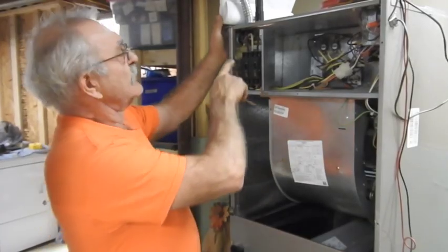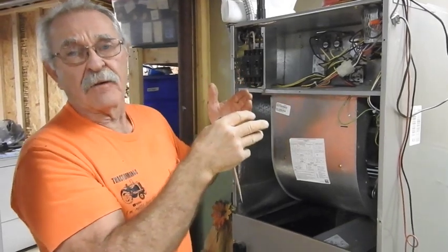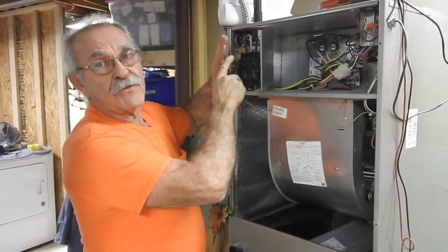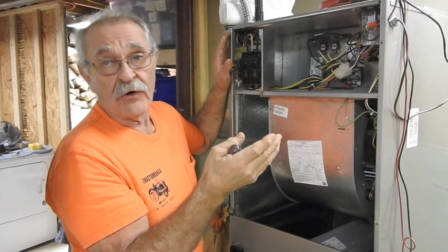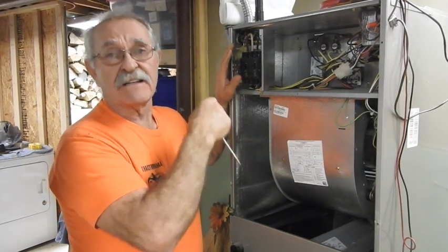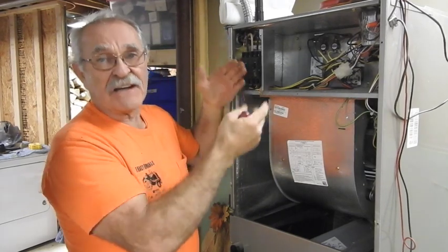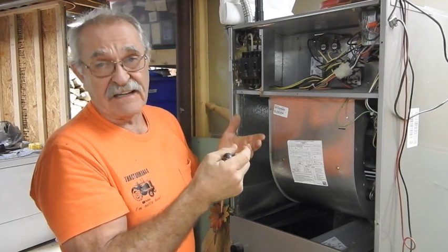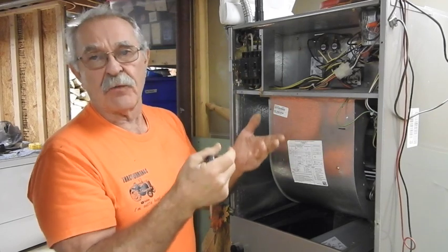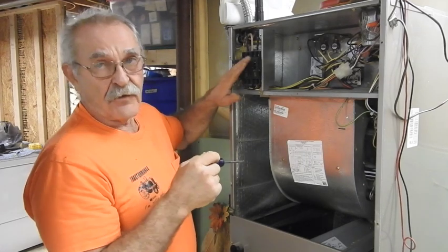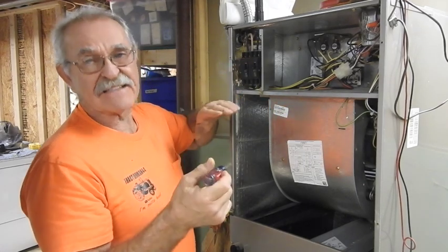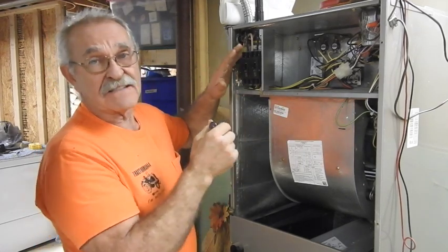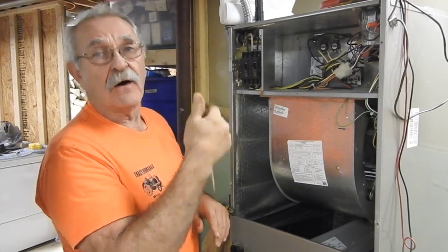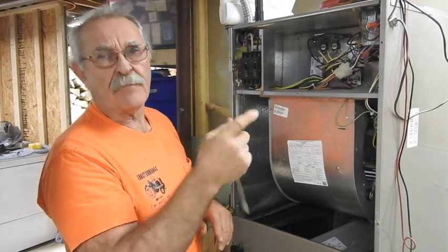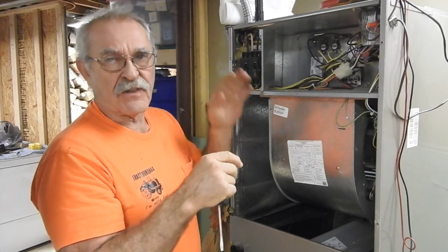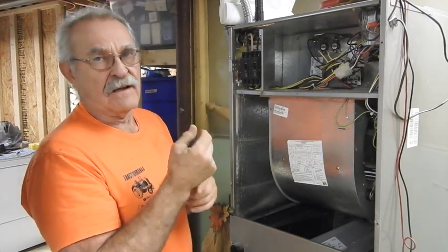I would also suggest if you're going to disconnect these wires and not reconnect them right away, do what you have to do to protect the ends of them. In the event you're not on the job site, somebody might get into the panel box checking for whatever and actually power these back up by accident, trying to find some problem somewhere else in the house. So either terminate these properly in the next appliance or secure the ends of the wires via large wire nuts or 10,000 volt electric tape, multiple wraps, in order to make sure that there can't be an issue.